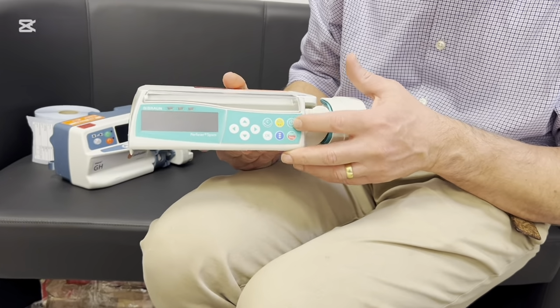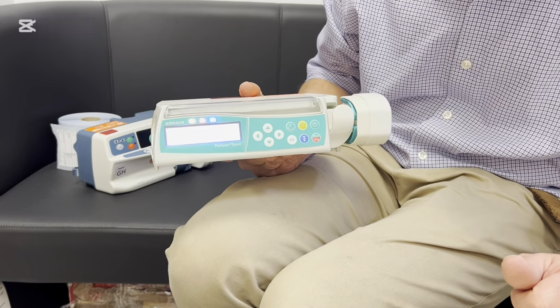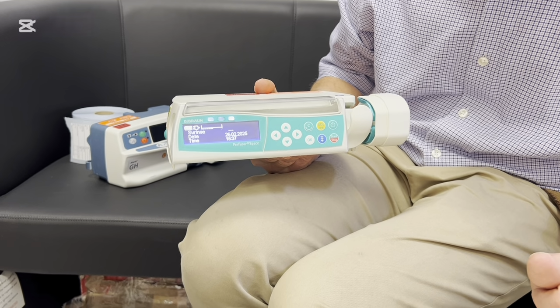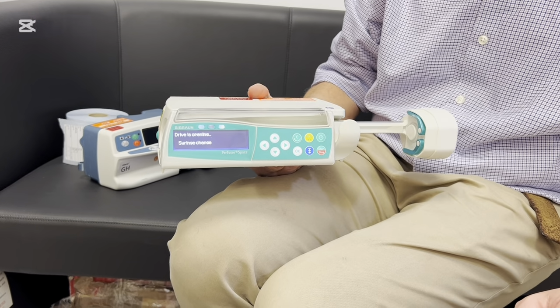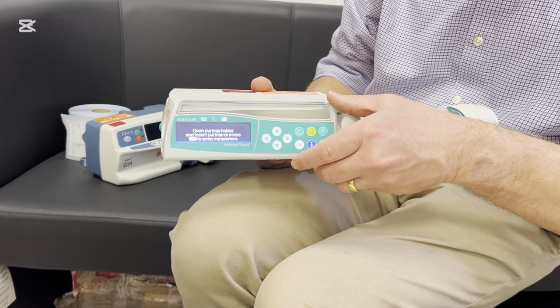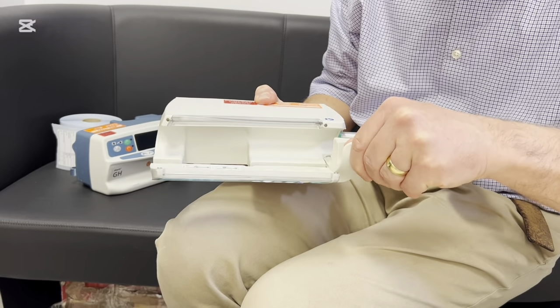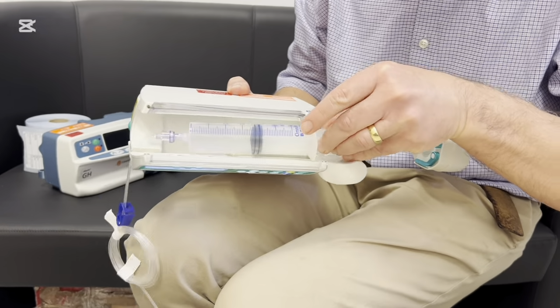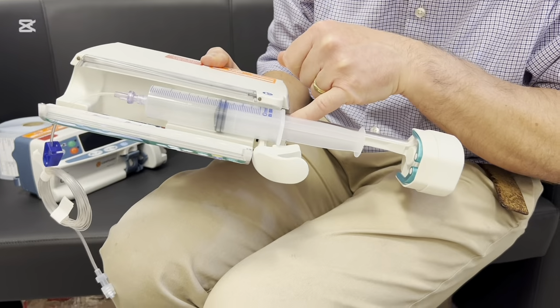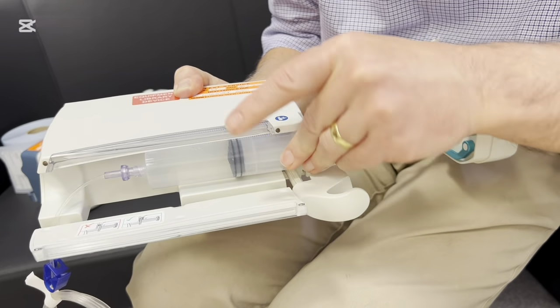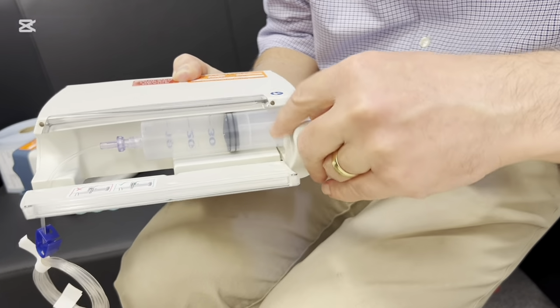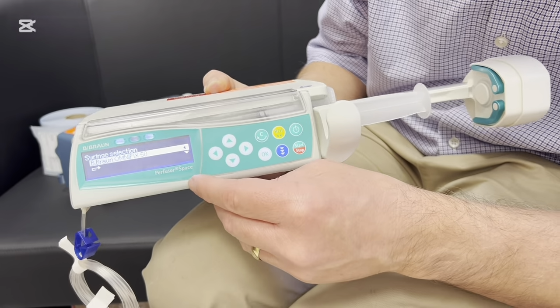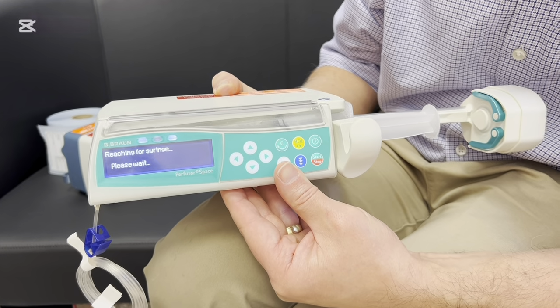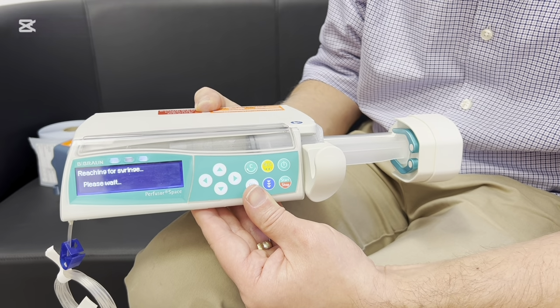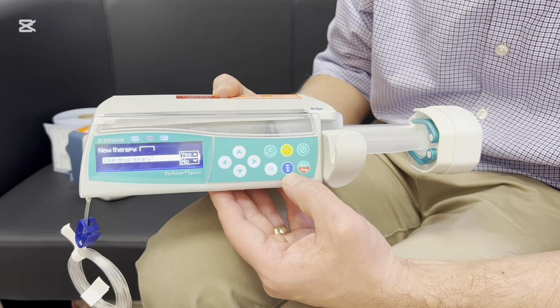So we'll turn it on, just like we did with the space pump for the volumetrics. It'll go through a self-test, and the arm will then extend and allow us to open the door to insert a syringe. So we open the door, pull this clamp out of the way, rotate it through 90 degrees, then we can put the syringe, which again is a B-Braun Omnifix syringe, into the syringe holder. We make sure that the lugs of the syringe go inside the green retaining clip there. Close the door, and it's going to say B-Braun Omnifix syringe, and I'm going to confirm that it is. Because it has advanced onto the syringe, it's taken up the mechanical slack and is ready to infuse as soon as you press start.